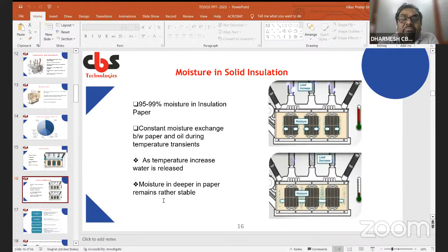These are the types of moisture which you normally see in transformers. There are 3 or 4 types of moisture which enter the transformer. First one is chemically bound water. This chemically bound water consists of glucose molecules. It gives paper its mechanical strength. It must remain inside the transformer, and it prevents over drying of the cellulose.